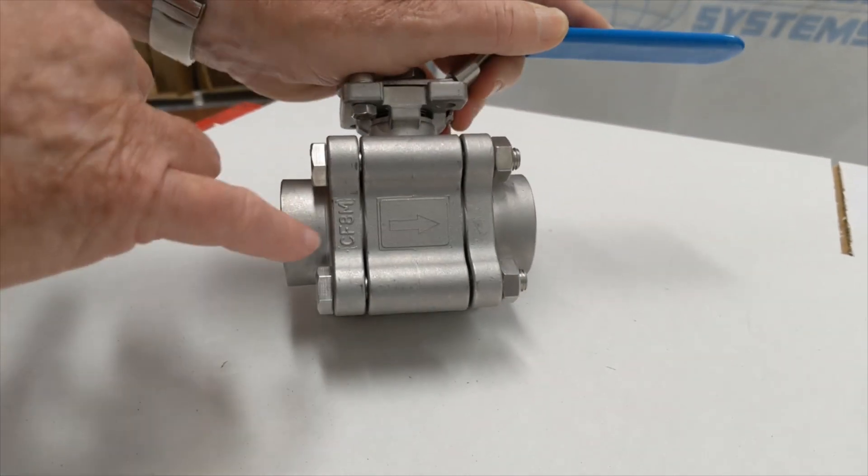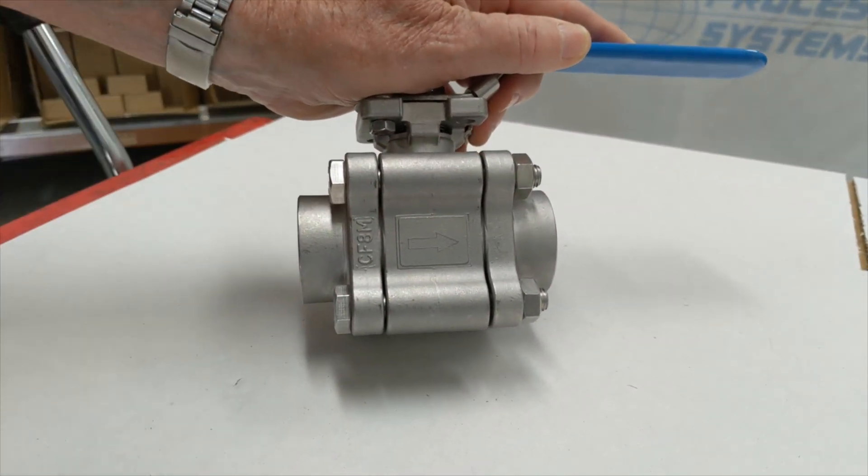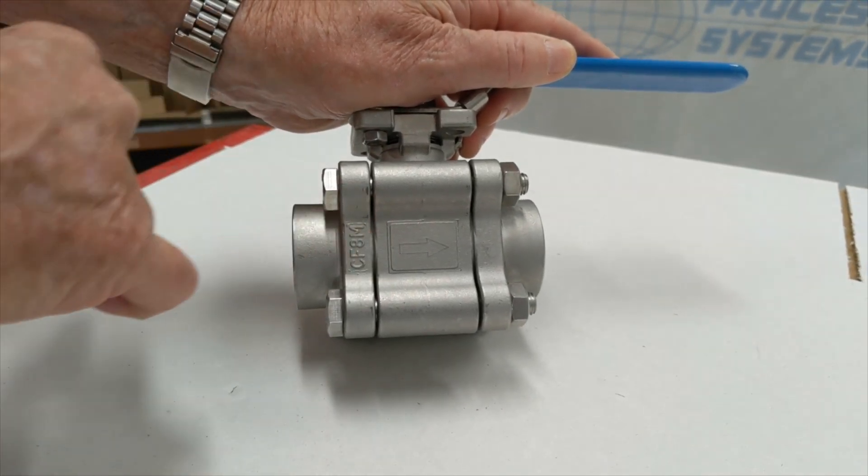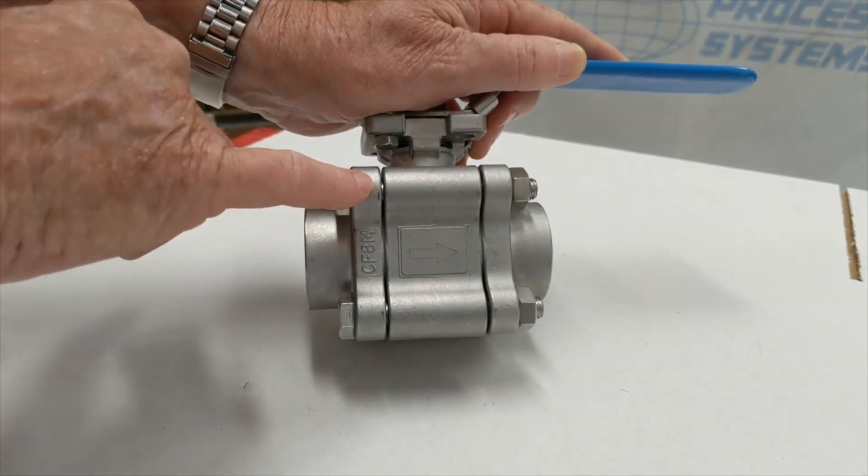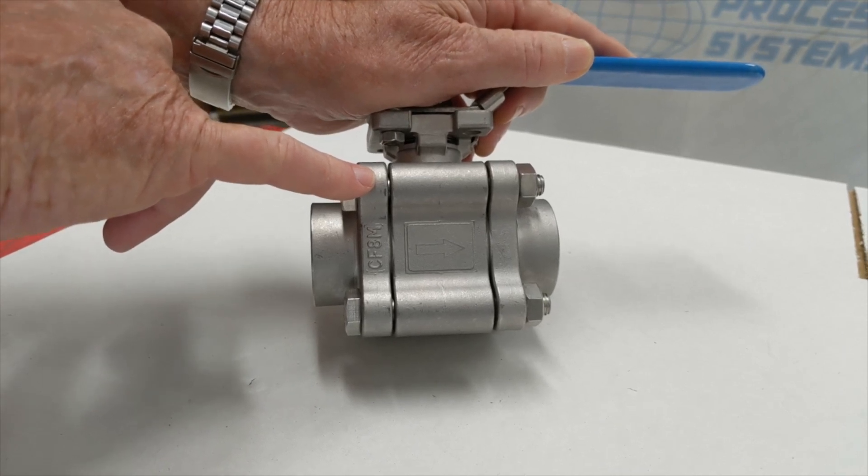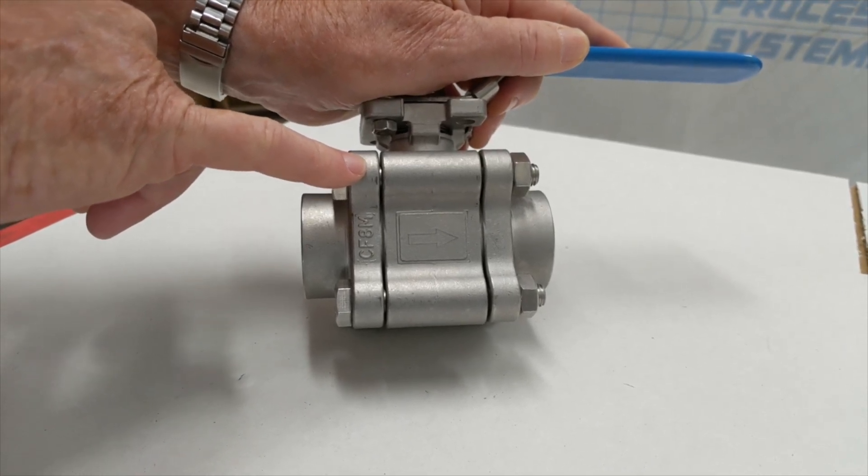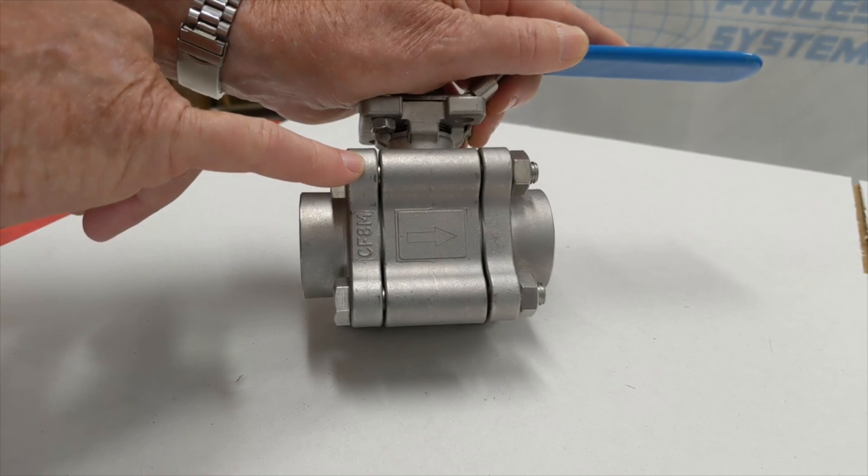It's a 40 bar valve, unidirectional. You can see the flow direction just here, the angle direction of flow. It has classification leakage to ANSI FCI 70.2 class 5.